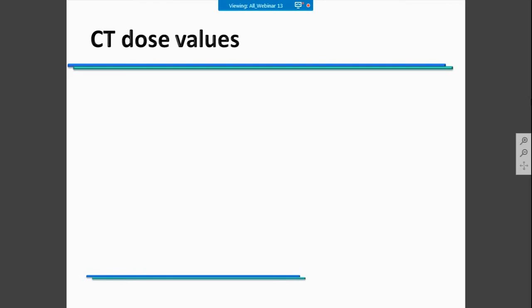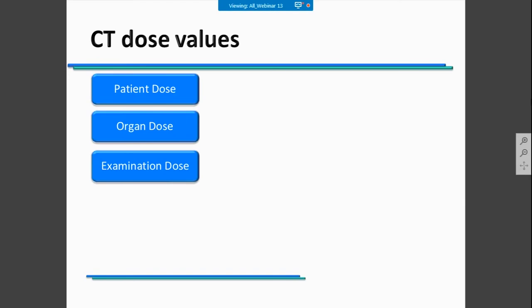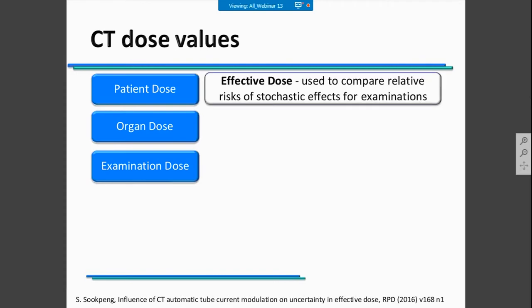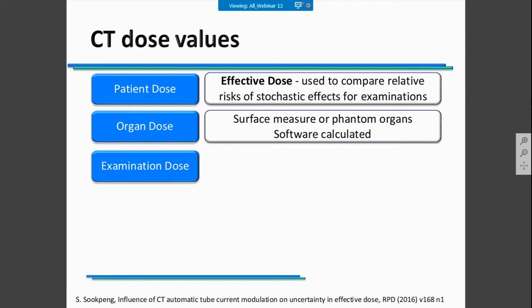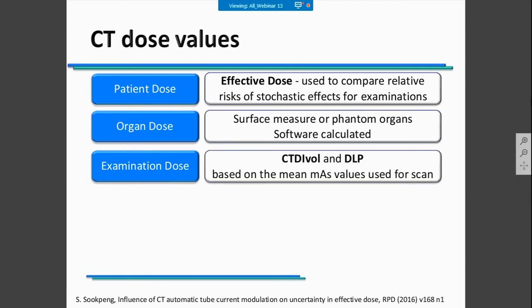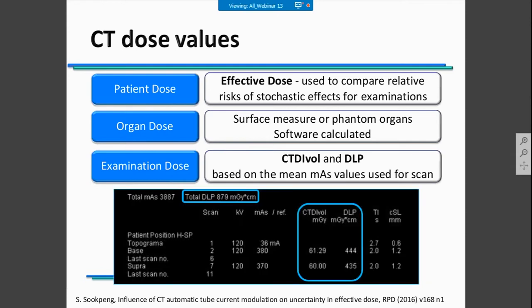CT dose values could be described in different modes. Sometimes we talk about patient dose, organ dose, or examination dose. Patient doses are normally described in effective dose and presented in millisieverts. Organ doses are also presented in millisieverts and they could be measured or software-calculated. Examination doses in CT are described as CTDI vol and DLP values, and they are available on our CT scanners every day.